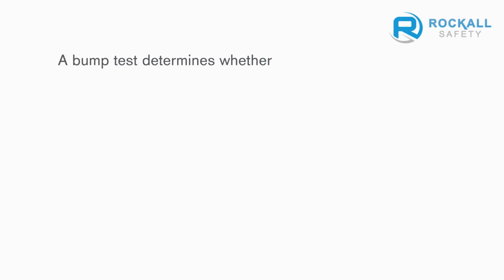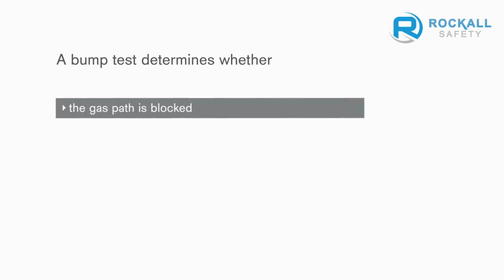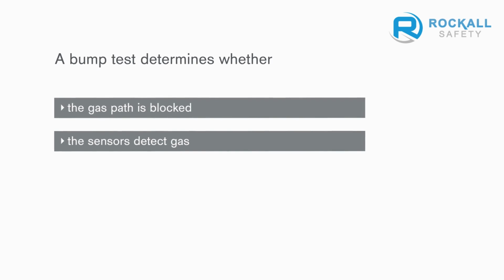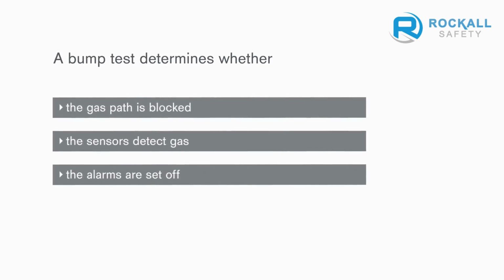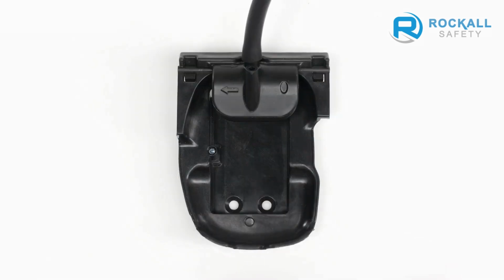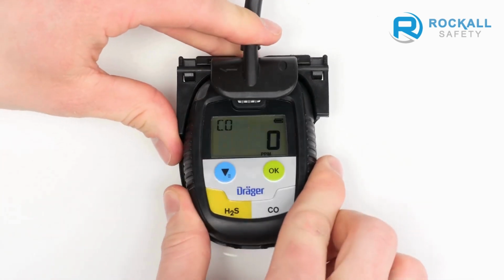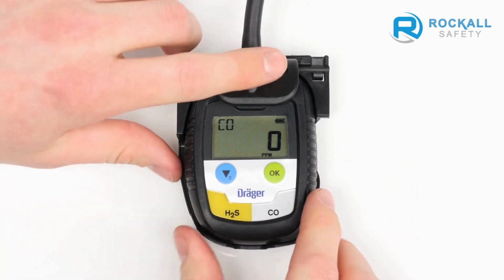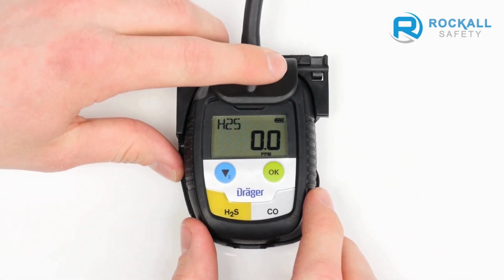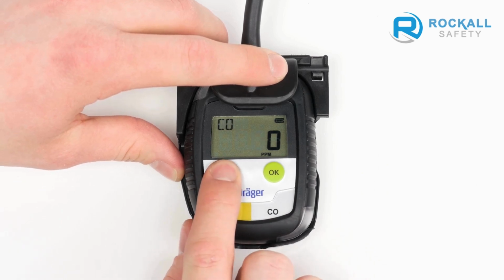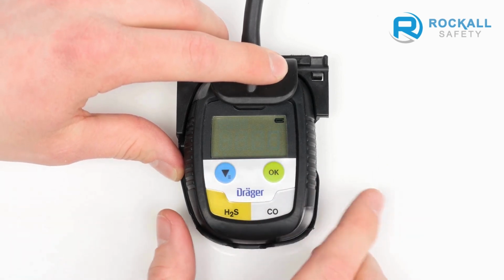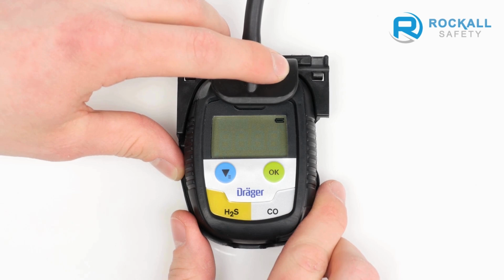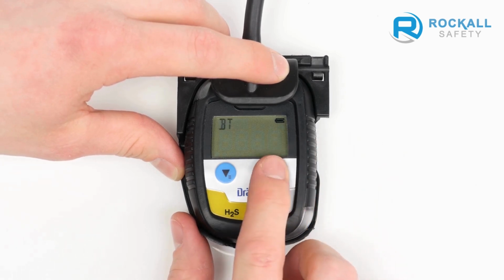A bump test determines whether the gas path is blocked, the sensors detect gas, the alarms are set off. In order to conduct a manual bump test, attach the device to a calibration adapter and connect the adapter to a test gas cylinder. Press the blue menu button 3 times in a row. Now press the OK button in order to start the test.